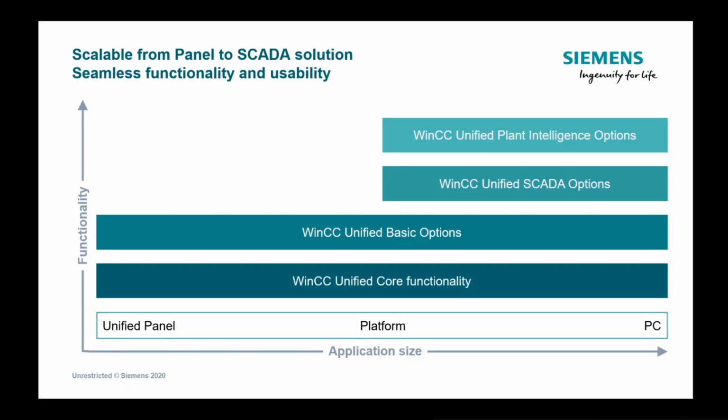So the WinCC Unified core functionality is supported across the panel and PC runtime systems, and the WinCC Unified basic options are also supported across the Unified panel and PC runtime systems. On the Unified SCADA options and the Unified Plant Intelligence options, so the last options we covered on that little wheel, these are only available on the PC-based platform. So here's a key demarcation. If you require the functionality of, for instance, a calendar or redundancy, your system needs to be a PC-based platform rather than a panel. So that's a little bit of positioning in terms of the options.